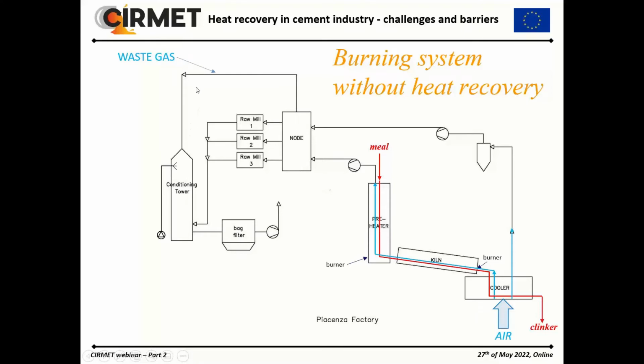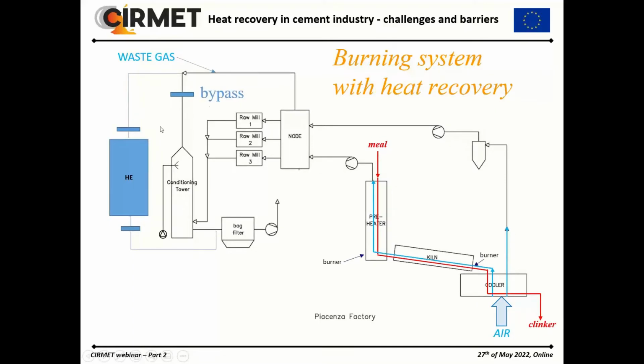So the temperature of the gases decreases from 300 degrees to about 150. There's a thermal loss, of course, in the conditioning tower. So we decided to install a heat exchanger to transfer the heat from the waste gases to an ORC system. So the gases, instead of passing through the conditioning tower, pass through the heat exchanger.